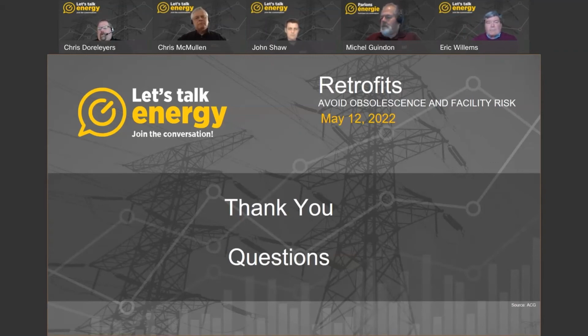Yep, thank you. I think single lines are really important. It gives us a 30,000-foot view of how we're going to integrate that unit for capacity, what type of paralleling devices are connected to it, what type of control, which helps us select what we need to marry up to the existing system. Even a sequence of operation is huge in terms of how the system's supposed to behave and operate - what generators come on, is it load sense, load demand, do we need any type of load rejection downstream, shedding of load, that kind of thing.